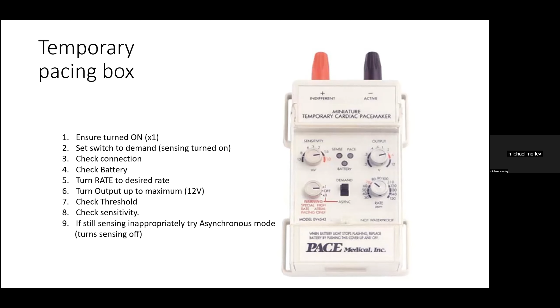So then we're going to have to check a few things to try and get our temporary wire working. So what we can do is we can turn the lower right-hand knob to the desired heart rate. So that's the rate that we want the pacemaker to make sure that the heart can't go slower than. And we can turn the output, that's the size and the magnitude of the impulses that are being sent down the lead, to the maximum. So we're going to turn that up to 12 volts. And for now, we're going to ignore the sensitivity knob on the left-hand side. Okay.